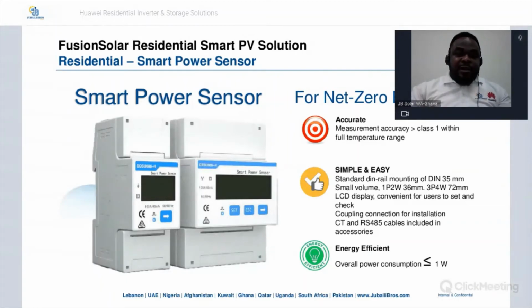Provided in the box of this smart meter will be CTs, current transformers. There will be one current transformer for the single-phase system, and three current transformers for the three-phase system. This is what helps you enable zero export in your system. So if you are designing any Huawei system for your house, and the country or regulator where you live says no export should be sent to the grid, this is the kind of meter you need to get installed in your system.